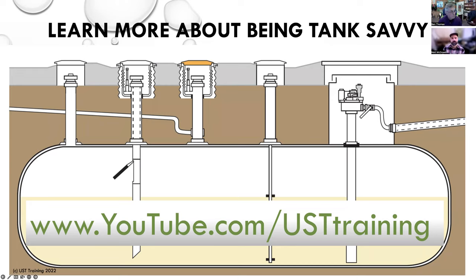Are there limits to the number of manifolded tanks? Are there practical limits that ATGs run up against with manifolded tanks? I seem to remember something about up to a certain size. There are certain limits to which a tank gauge will function if the tank is too big, but normally it's two tanks manifolded together. I don't know if I've ever seen more. Maybe at giant truck stops, there might be. So it's normally two identical size tanks manifolded together, and they should have the exact same volume in each tank, because as it drains down, it's pulling from both tanks. But you do need to isolate those to do that. But I think if you're doing CSLD testing, you don't have to isolate the manifold. I have to double check on that.